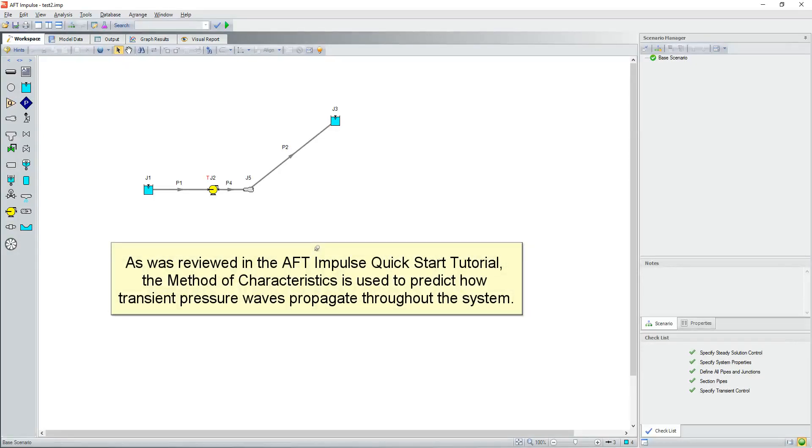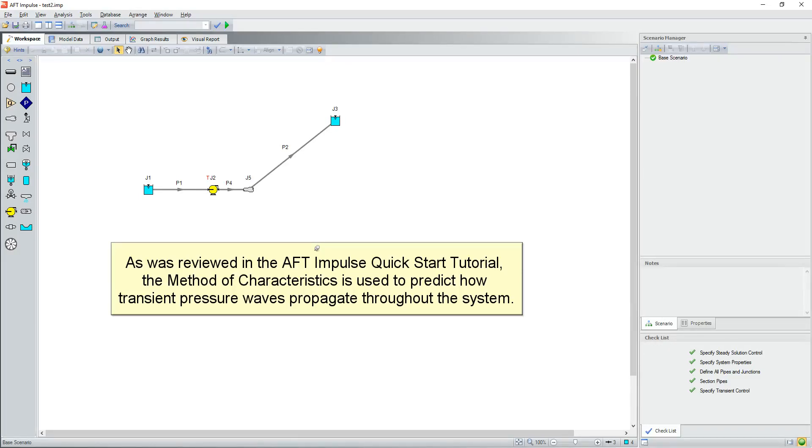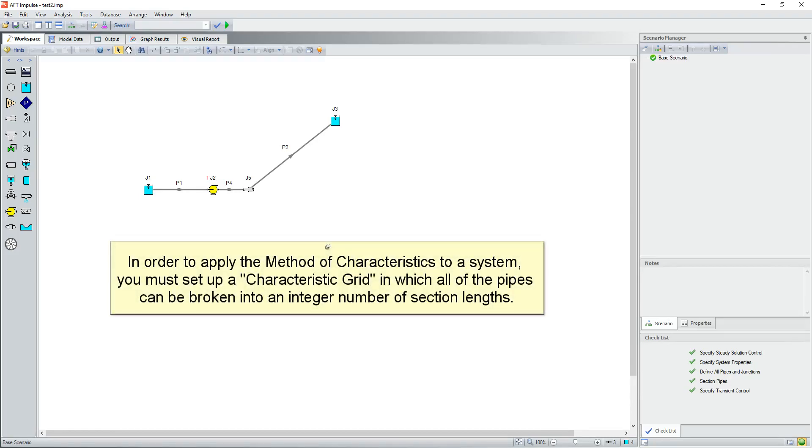As was reviewed in the AFT Impulse Quick Start tutorial, the method of characteristics is used to predict how transient pressure waves propagate throughout the system. In order to apply the method of characteristics to a system, you must set up a characteristic grid in which all of the pipes can be broken into an integer number of section lengths.